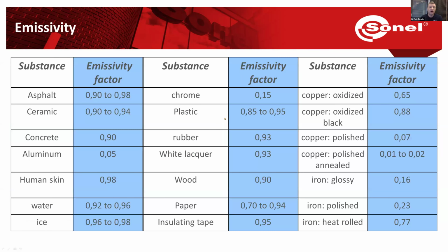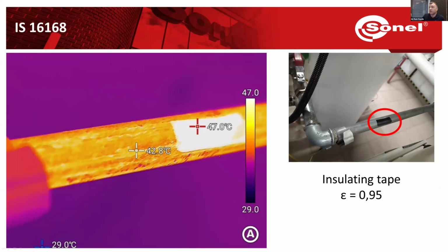Now, in the manual and on the higher models of the cameras, we can find a table with emissivity values for different types of substances. Like asphalt, ceramic, aluminum, human skin, wood, paper, iron, and so on. But what if we have, for example, concrete which is painted? Then we would not know, because concrete has 0.9, but maybe the paint is influencing it. And for that reason, this is actually why the standard recommends to have insulating tape with you.